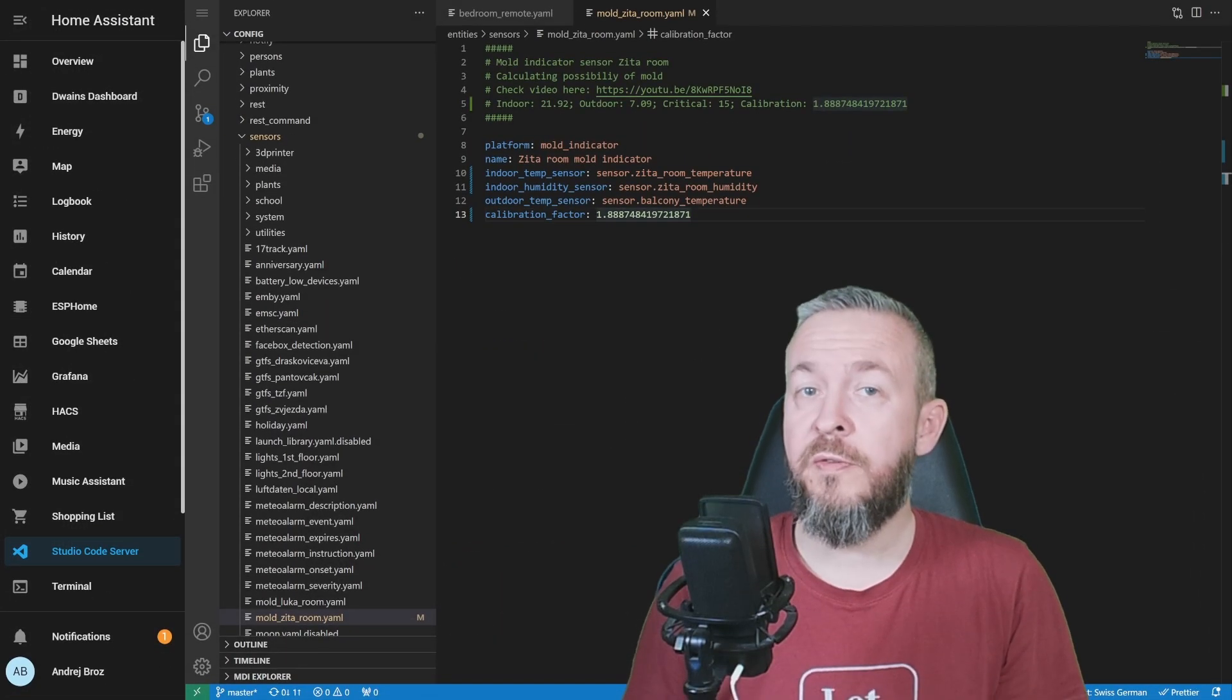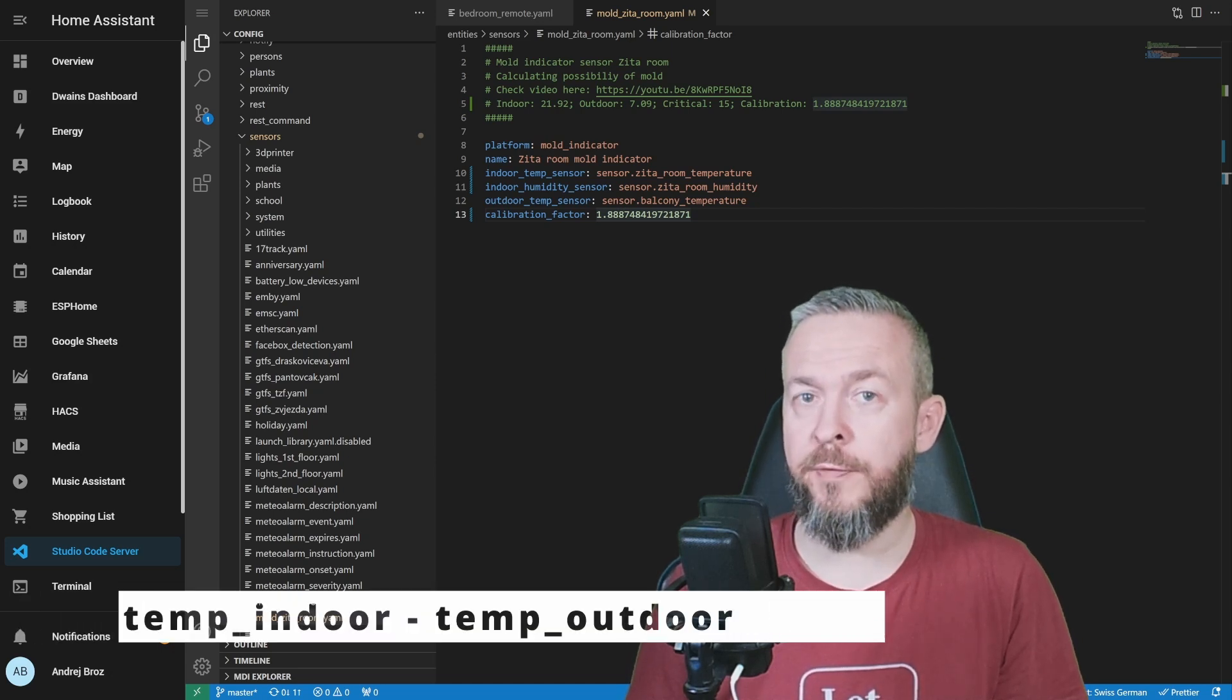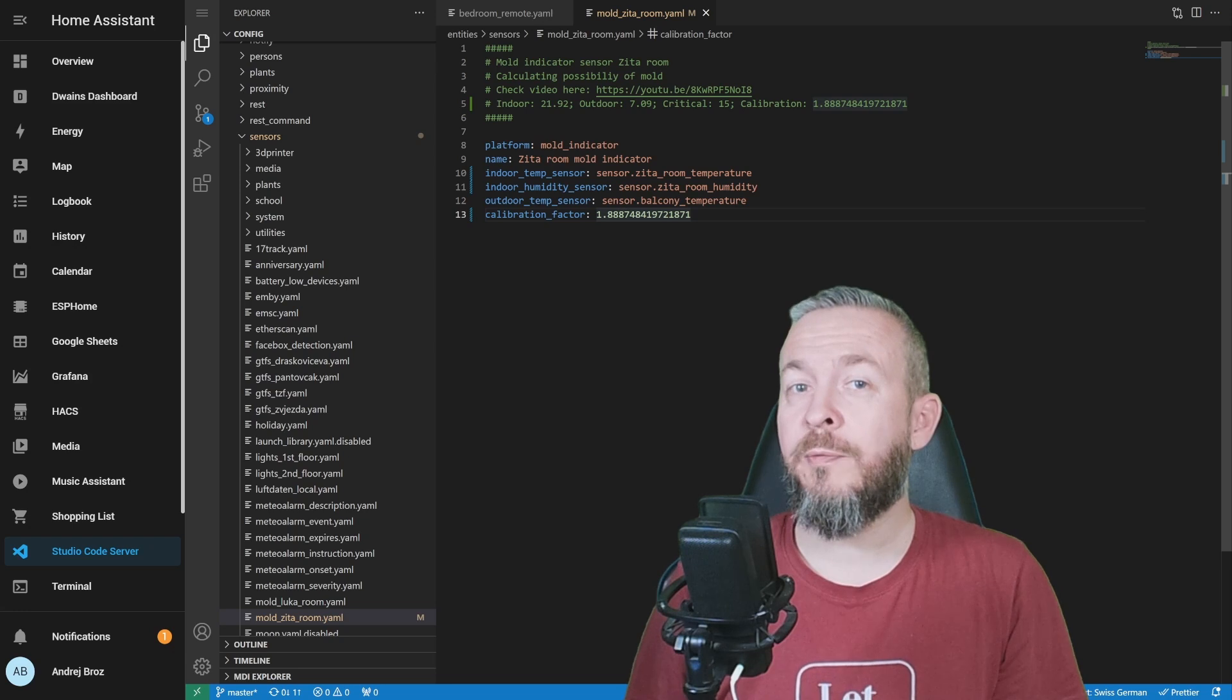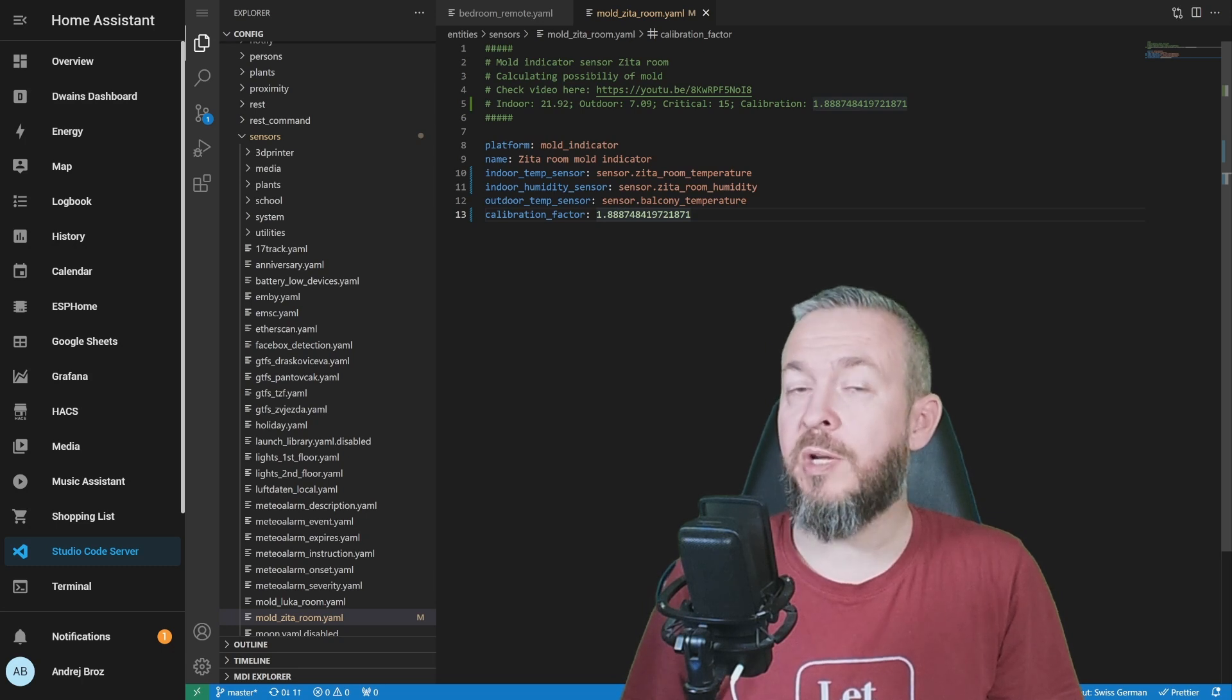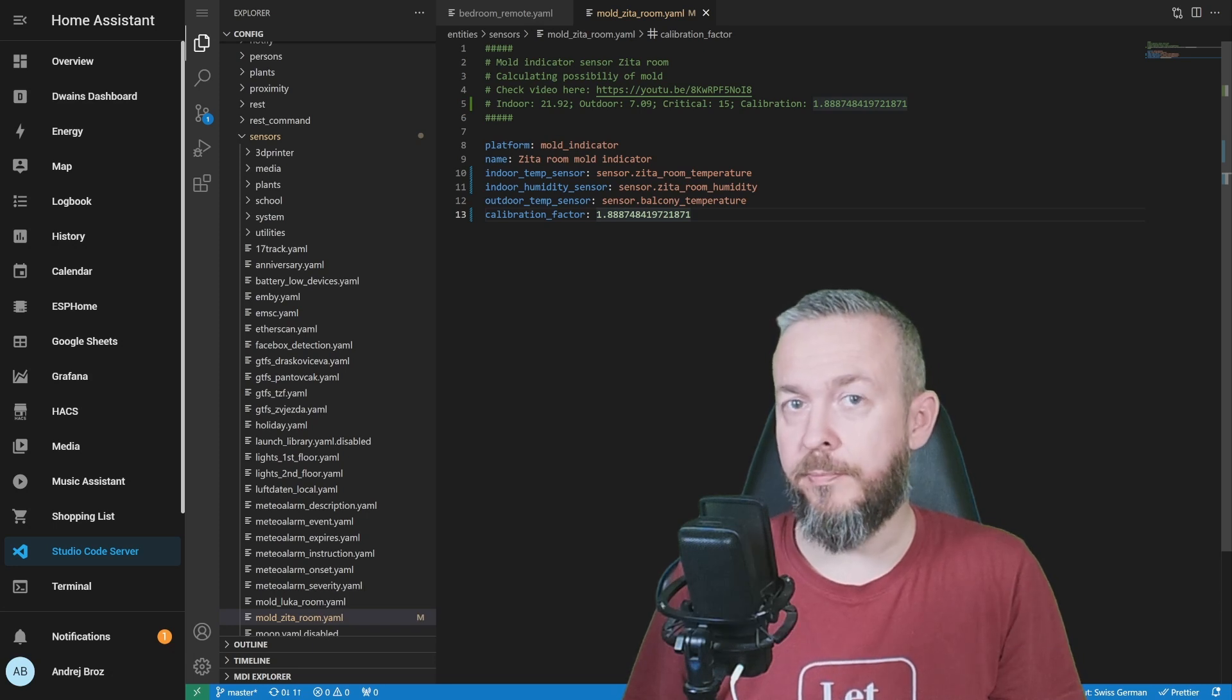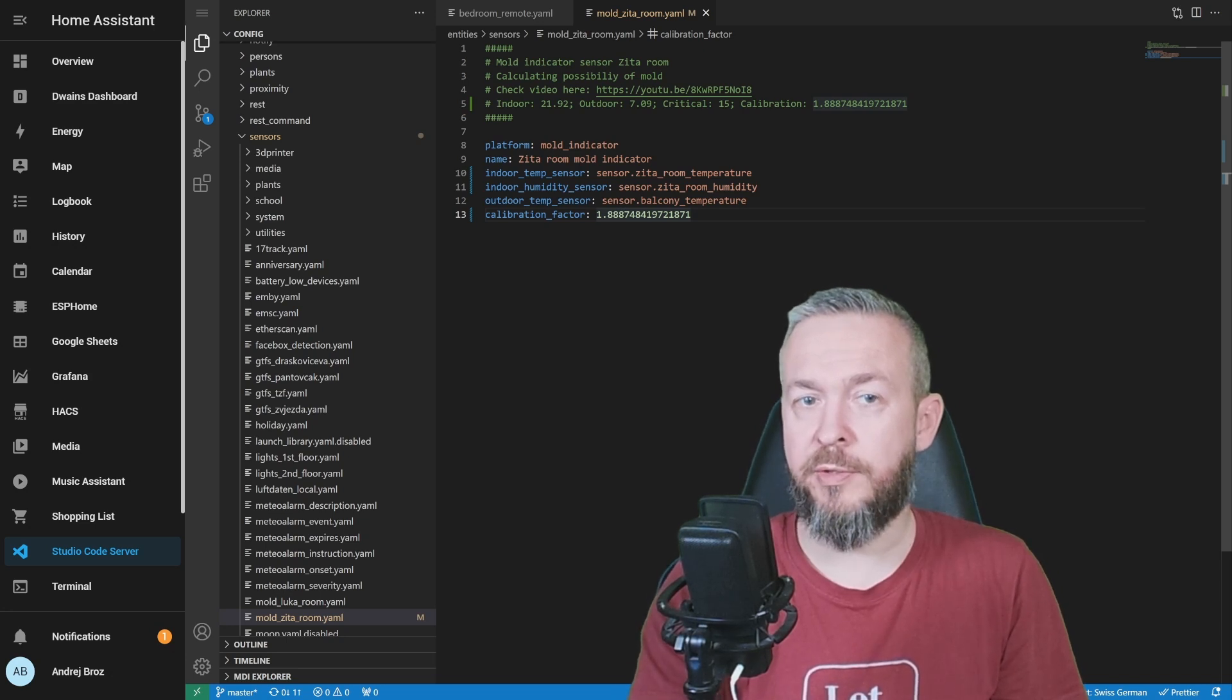Calibration factor has to be calculated. First, you need to subtract outdoor temperature from the indoor temperature values. The next temperature you need is the temperature of the wall. You have to find the coldest spot. For me, this was the corner of the room facing outside. And then you have to subtract the outdoor temperature value from this coldest spot in the room. First value is then divided by the second value, and you get the calibration factor.